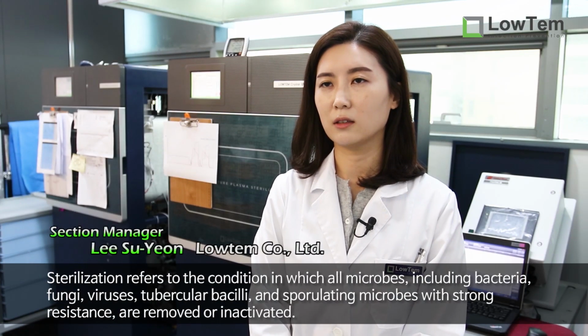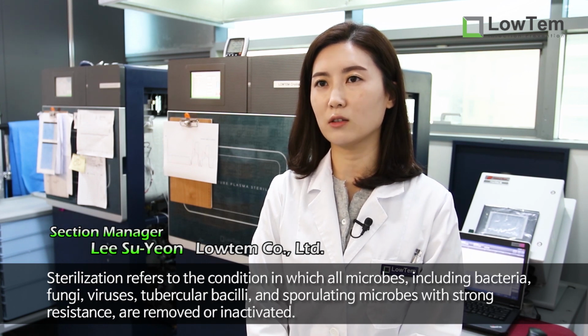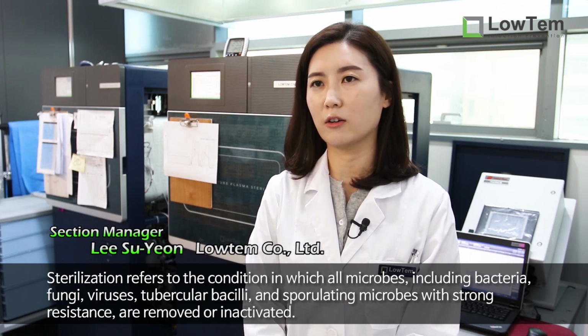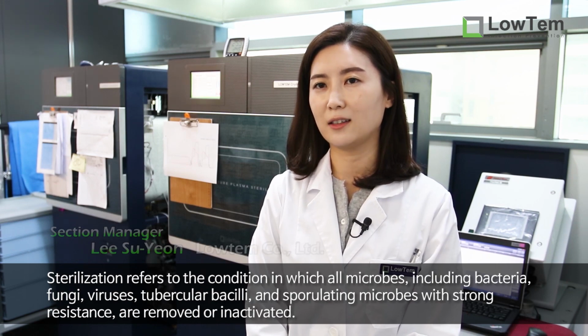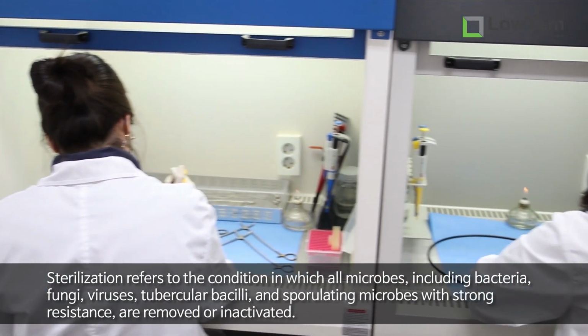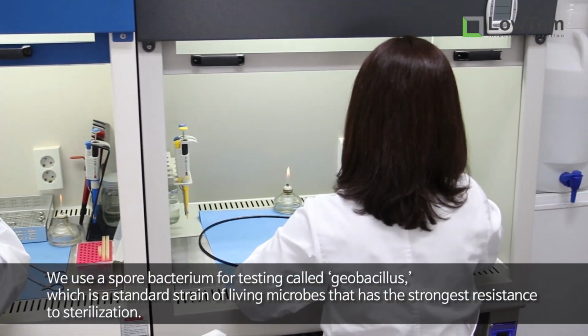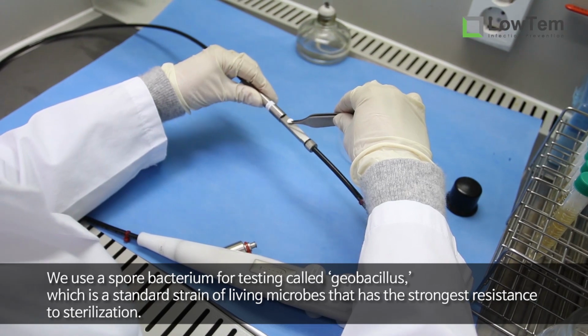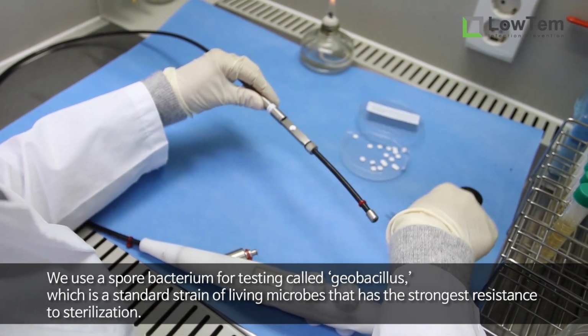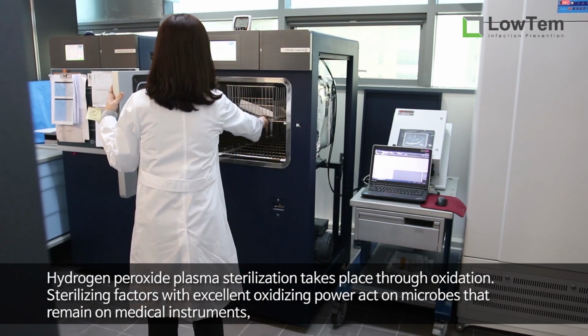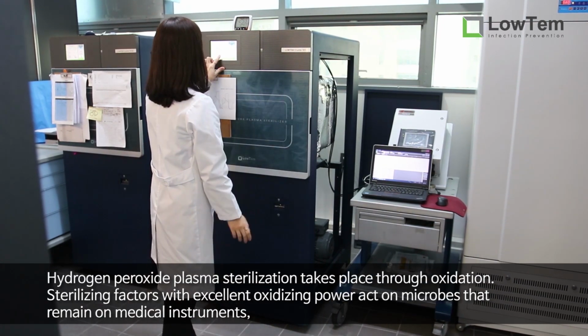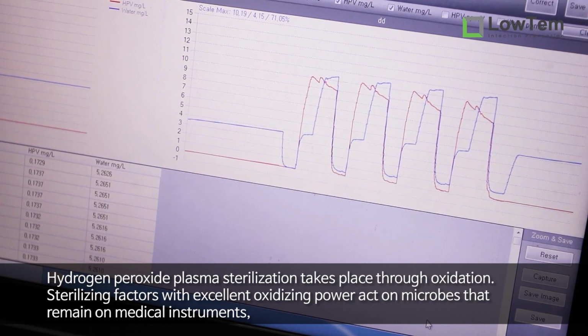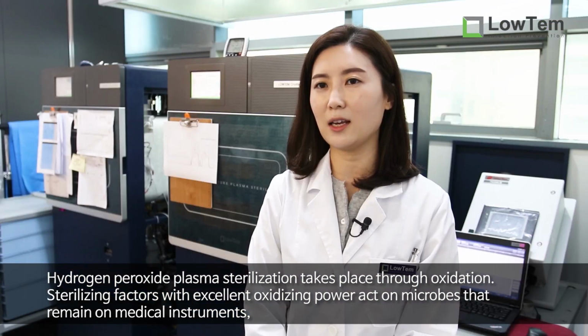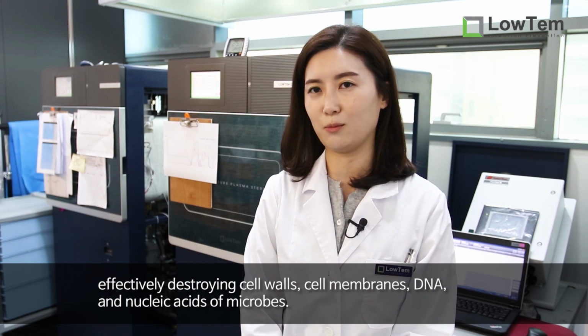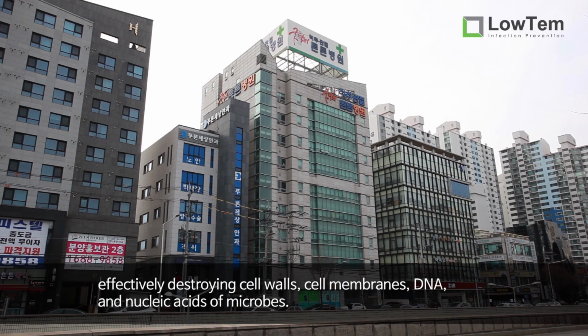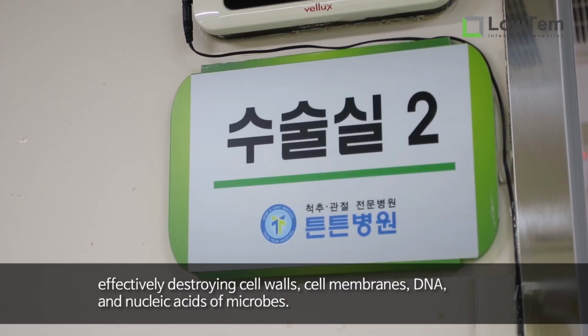Sterilization refers to the condition in which all microbes, including bacteria, fungi, viruses, tubercular bacilli, and sporulating microbes with strong resistance are removed or inactivated. We use a spore bacterium for testing called Geobacillus, which is a standard strain of living microbes that has the strongest resistance to sterilization. Hydrogen peroxide plasma sterilization takes place through oxidization. Sterilizing factors with excellent oxidizing power act on microbes that remain on medical instruments, effectively destroying cell walls, cell membranes, DNA, and nucleic acids of microbes.